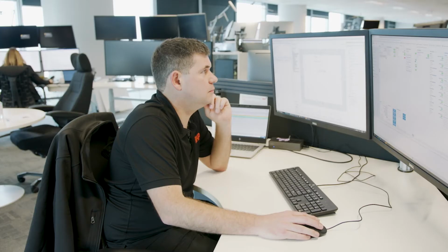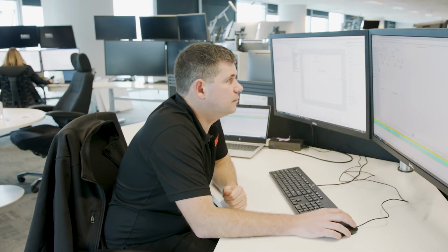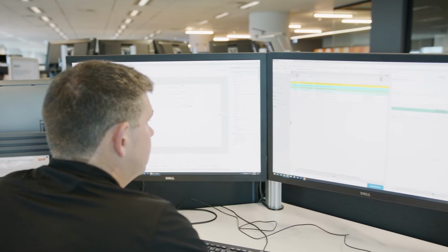The unique aspect of this project was that we developed a custom OPC UA connector for Ignition. This allowed us to integrate directly to our OSIsoft PI infrastructure across Australia. In doing so, we actually watch and collect live data as it streams into the interfaces in OSIsoft PI, even before it's written to disk.